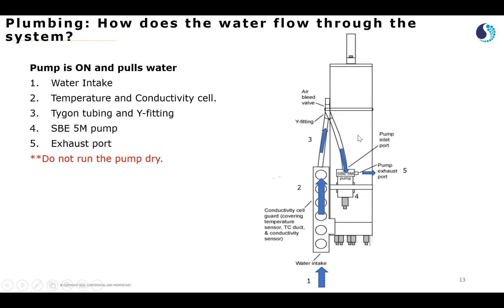It is important to note to not run the pump dry for more than a second or two. It's also important to note that the water is being pumped constantly, because if that's not done, there are issues with the data, and you can have drift in temperature, conductivity, and if you have other auxiliary sensors such as dissolved oxygen, you'll get issues with that data.